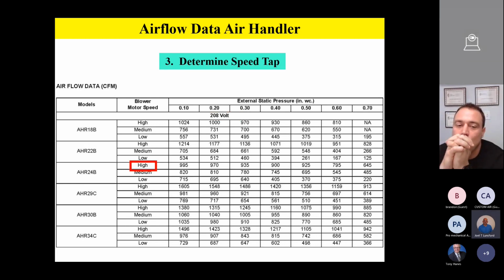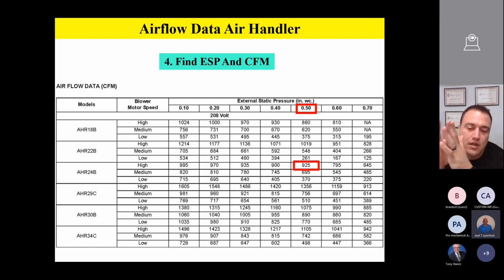Step number 3, determine what speed tap you're on. So physically look at the motor and see what speed tap you're on that you're testing your airflow. So whatever speed tap that is. So let's say it's high speed tap in this example. You'll then go over and you'll look at your external static pressure that you measure. And then you'll come down and you'll correlate with the air handler and the speed tap on the appropriate chart, based on voltage if applicable, and you'll read your CFM.